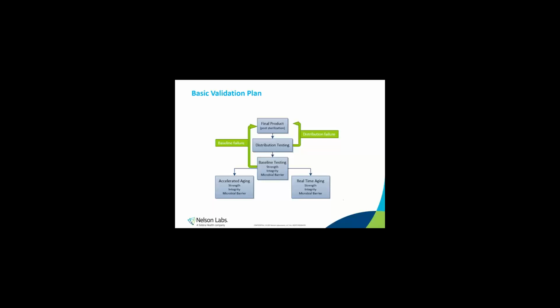So you can use accelerated aging at temperatures up to 55 C to speed up the process. It only takes 7.5 months to get a 5-year accelerated age product. You can submit to the notified body with just the accelerated data, but you're required per ISO 11607 to start the real time within 3 months of the start of the accelerated portion. And this is really just to ensure that the real time isn't forgotten. The aging time points are chosen by you and based on what you want your label claim to be. You must test baseline or time 0 and the final time point. But sometimes people include an interim time point as an insurance policy in case something unexpected happens at the final time point.